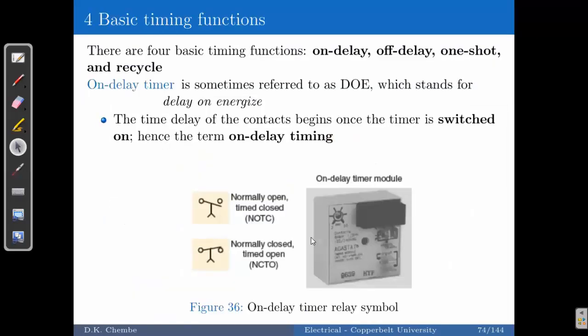There are four basic timing functions to understand. The two common ones are on-delay and off-delay, but we also have a one-shot and a recycle. A recycle is a cyclic, repetitive operation. The on-delay timer is usually referred to as DOE — delay on energize. These timers begin timing once the circuit has been switched on or energized. On-delay timers have a standard symbol where the arrows are pointing upwards, indicating an on-delay timer.